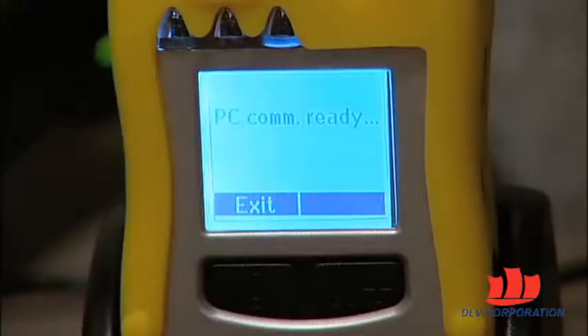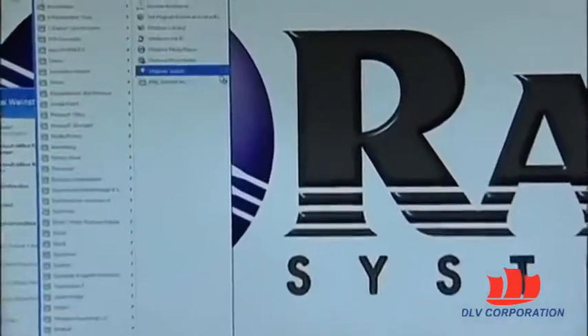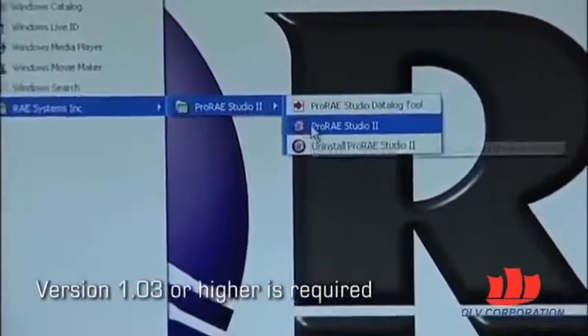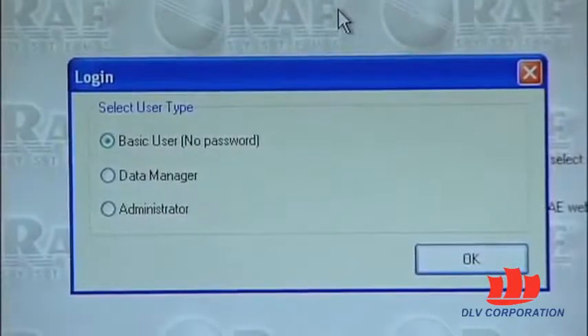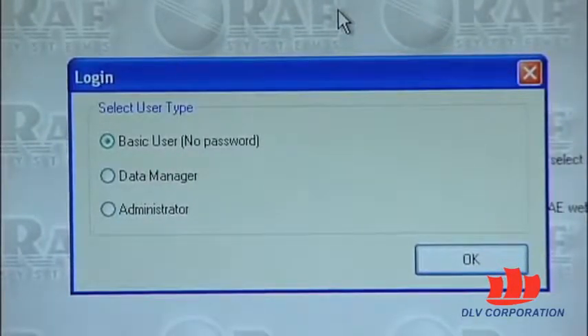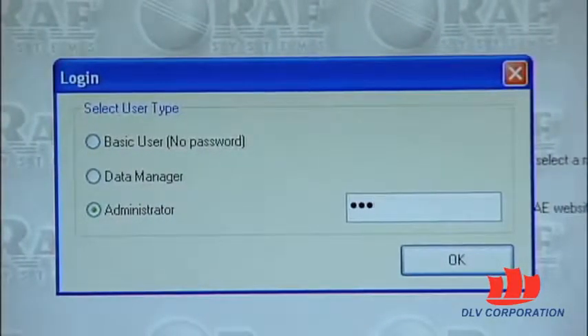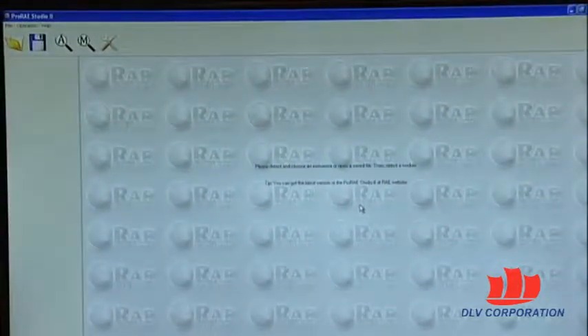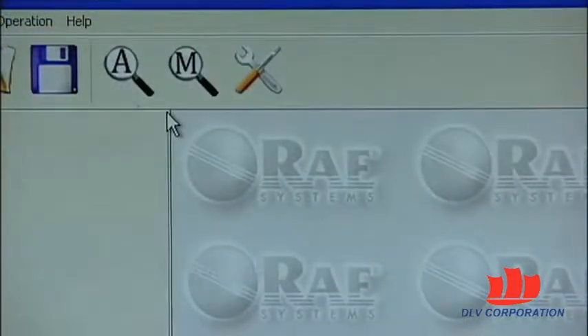Now your ToxiRAE Pro is ready to communicate with the PC. The next step is to load the ProRAE Studio 2 instrument configuration and data management software. ProRAE Studio 2 version 1.03 or higher will support the ToxiRAE Pro family. When the software loads, you're taken to the login screen. Log on as an administrator — the default password is 'RAE' all lowercase. After you've logged in, before performing any other operation, you must tell ProRAE Studio 2 to detect your instrument. The easiest way to do that is to use the automatic detect function.